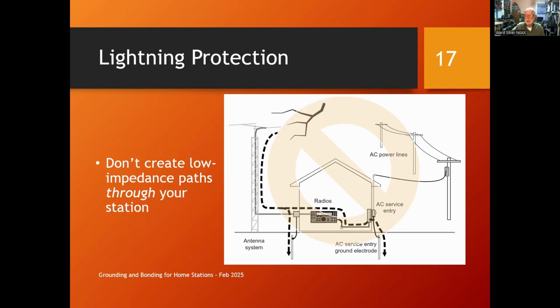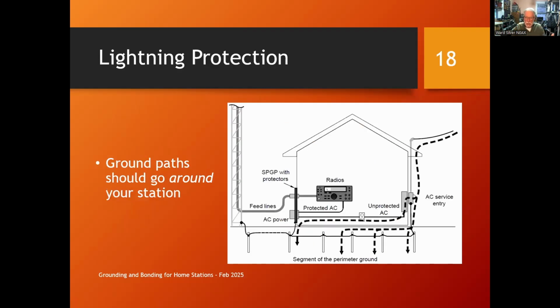So not only am I going to cause a voltage difference by flowing through the dirt, I'm going to flow through this radio station on my way to the other ground rod. And that causes lots and lots of damage. So you want to not have this low impedance path through your station. You want it to be outside your station.